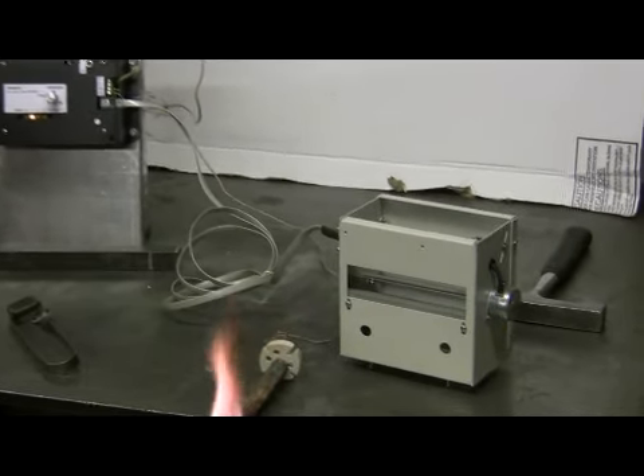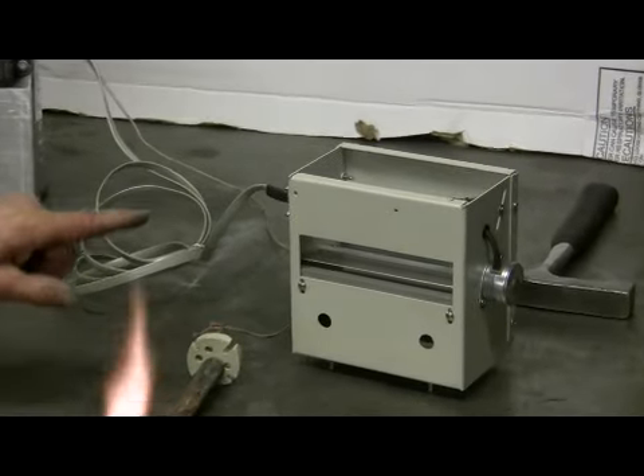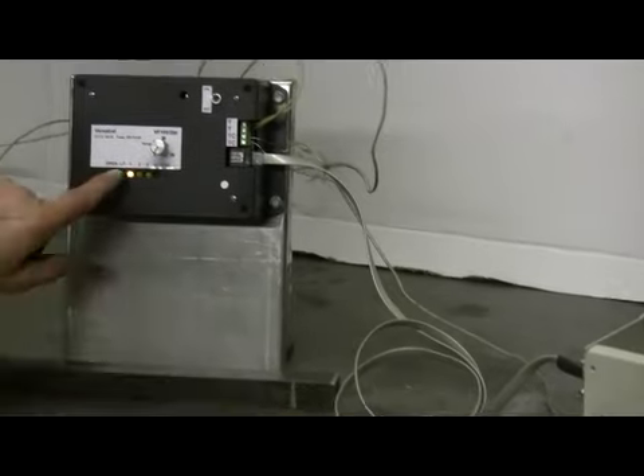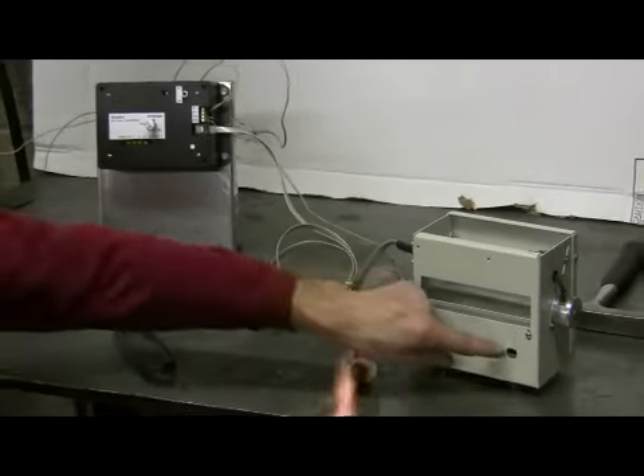There we go. Now you can see that the air shutter has gone to the second level, which was a ½ inch open. When two lights are on, it's a ½ inch open. When one light is on, it's a ¼ inch open. And now when it reaches your level of burn, which is low, I got it set on low, the air shutter closes and it goes on pilot air.